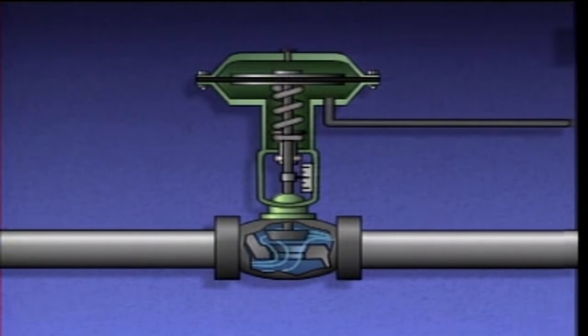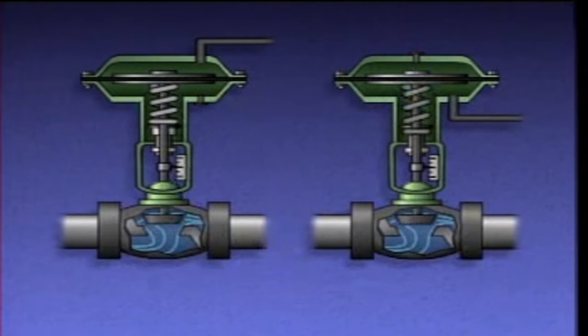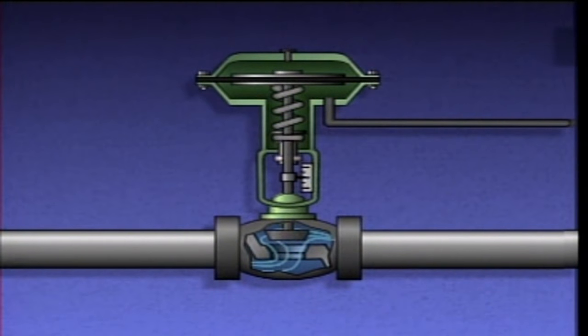A single-acting diaphragm actuator designed to close a valve — or fail closed — when air pressure is lost looks similar to the actuator just described. During operation, air pressure is fed into the lower chamber.